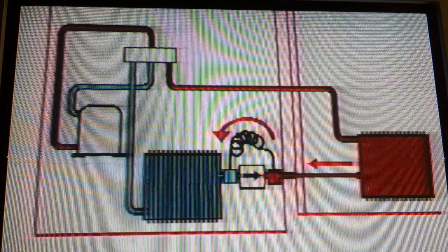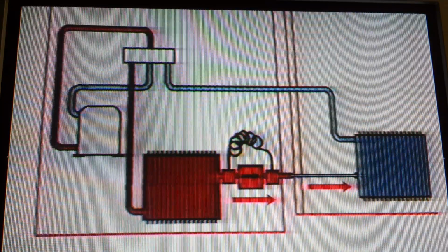The heating cycle requires more restriction than does the cooling cycle, so the check valve forces flow through both restrictors. The liquid line restriction then is the total of both restrictors. In cooling, one restrictor is bypassed by the check valve, leaving only the other restrictor for metering. Refrigerant metering, while more complex in a heat pump, is normally very reliable and contributes much to efficient evaporator performance.